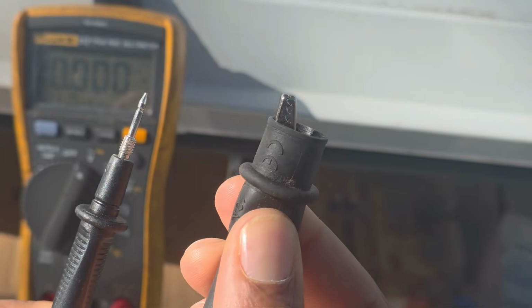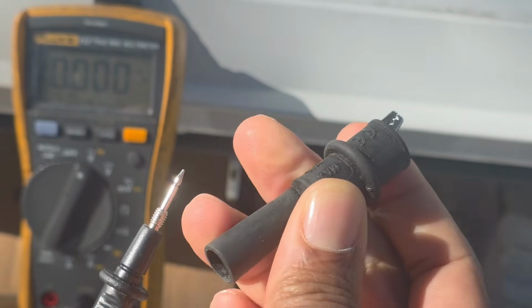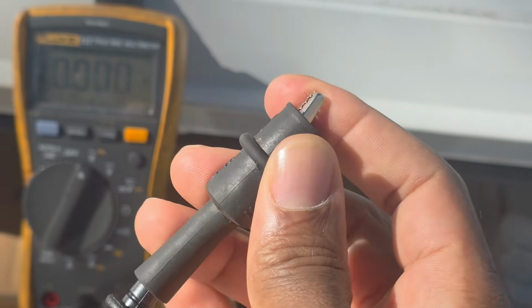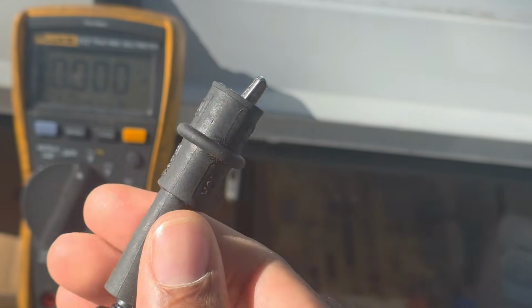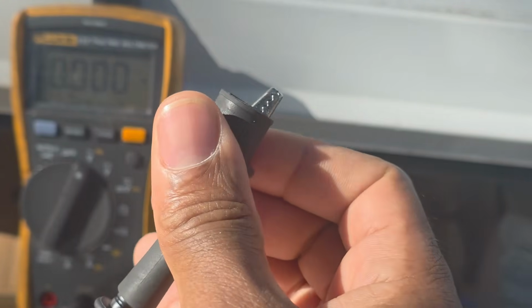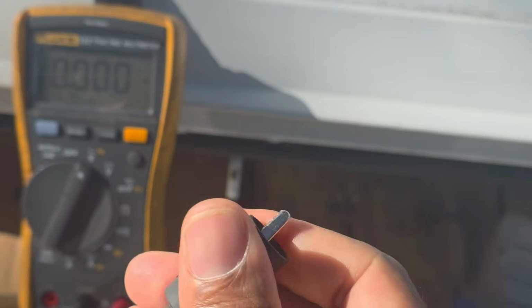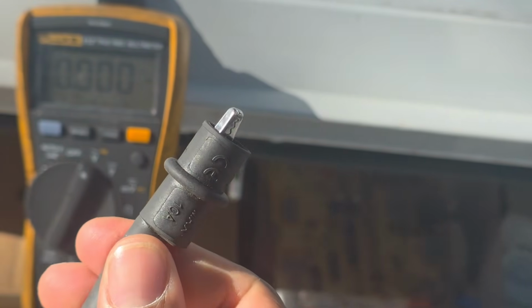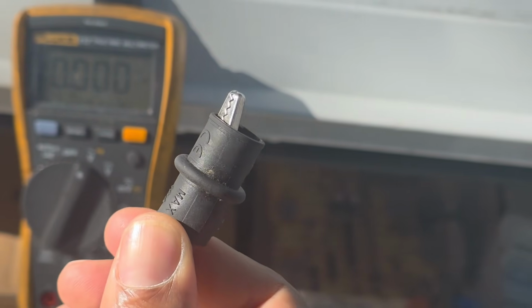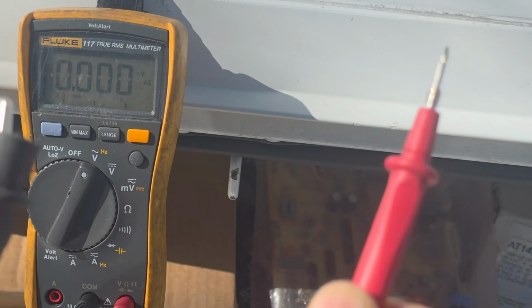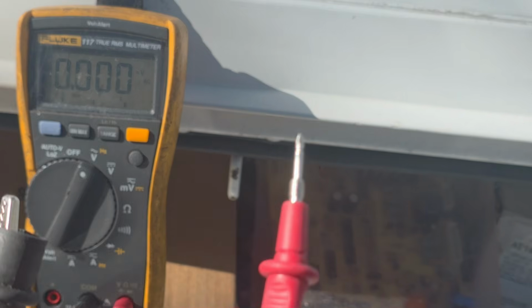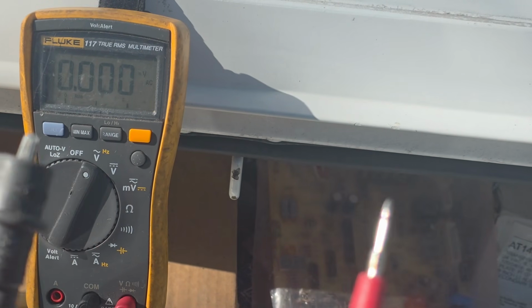Good way to have this planted at all times: get you a good alligator clamp to make it easier. The alligator clamp just screws down on this lead right here. This is going to be the one that's planted at all times. It's your pivot foot right here. This is going to be the pivot foot, and this is going to be the lead that we rotate. Like I say, this has to be in voltage. So we're checking this live.